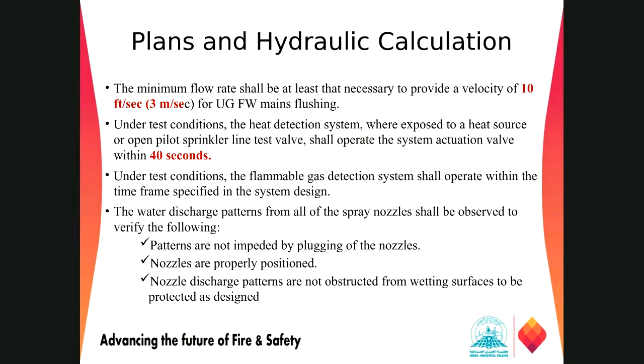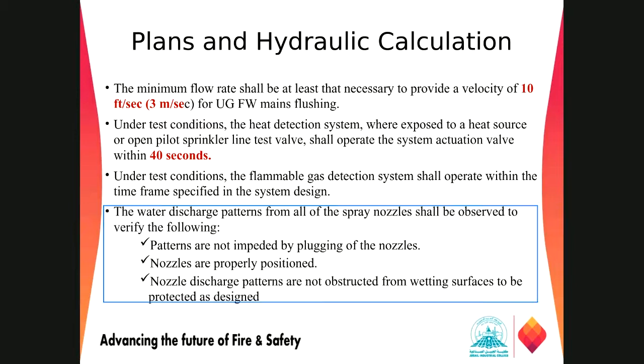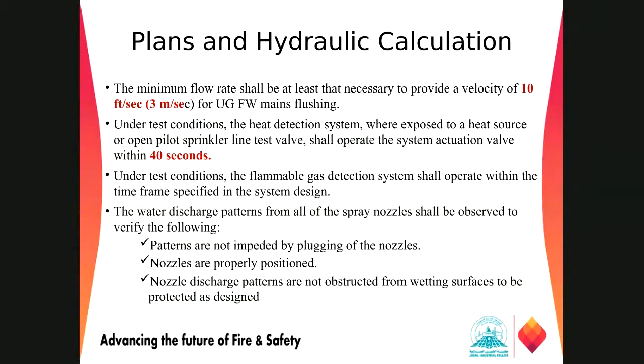And the last one we have regards the water discharge pattern from all the spray nozzles, which shall be observed to verify the following. So we have to verify the patterns are not impeded by plugging of the nozzles. If we are getting correct discharge from the nozzle side, we have positioned the nozzle correctly. The position of the nozzle is much more important in this area because these nozzles are based on angles, right? So we have to worry about the angle of the nozzles where we are going to protect. If the nozzle is not at the recommended angle, it will not protect the area, so it will not be cooling the surface in case of fire.